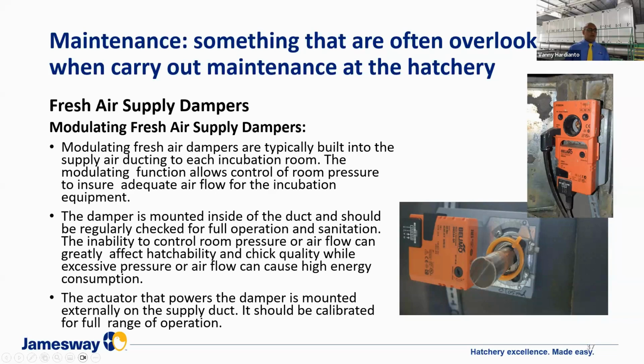The inability to control room pressure or airflow can greatly affect hatchability and chick quality. Also, excessive pressure or airflow can cause high energy consumption as well. The actuator that powers the damper is mounted externally, outside of the air supply duct. It should be calibrated for the full range of operation, calibrated for the closed position and the open position.